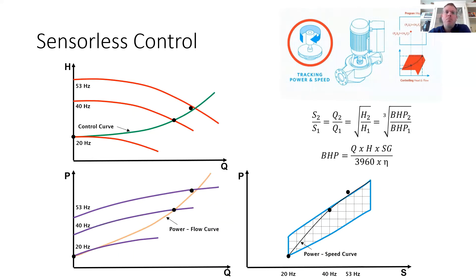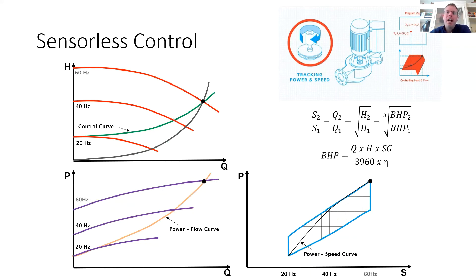So again, as valves start to open in the system, your flow is going to increase and your head will decrease in that same square root relationship. So the resulting power consumption at that given speed is going to increase, taking you off the control curve. So in the opposite fashion, the pump controller will speed up the pump until it reaches the appropriate power consumption.